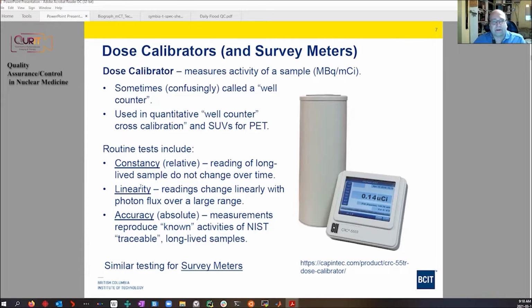Another test is called linearity. It's just testing the response over a range of activities, so that for high and low activities, we see that there are no systematic errors, and we also know the limits of what it can read. I'm not going to go through how these are measured. One of the tests I want to mention, though, is what's called an accuracy test. This is an absolute measurement of accuracy. So in the nuclear medicine department, there's a set of samples with known activity, long-lived radioactive samples that are NIST traceable. If you're not familiar with this concept, NIST is the National Institute of Standards and Technology in the States. They're the guardians, the keepers of the standard physical measures.